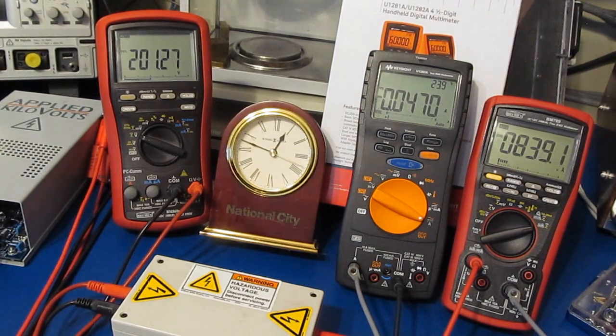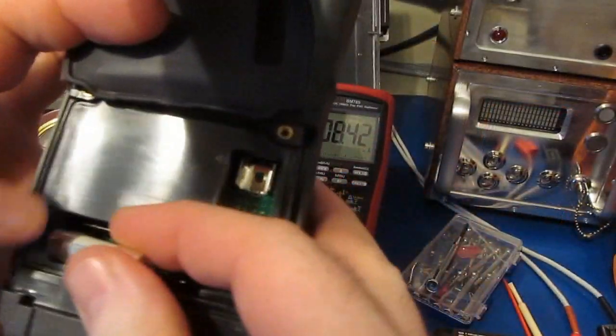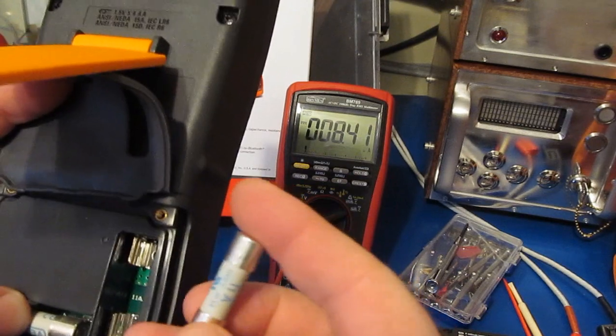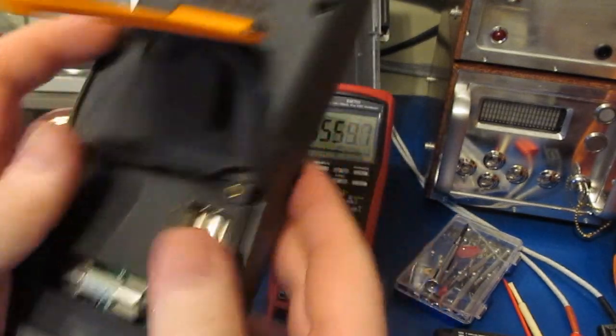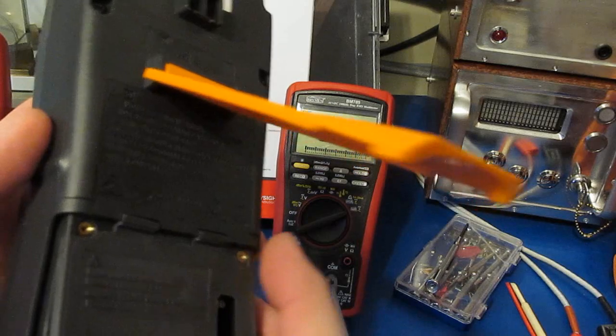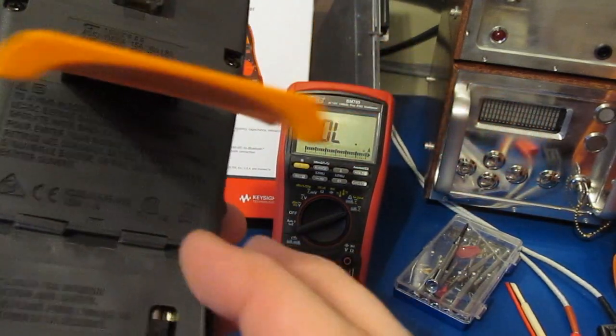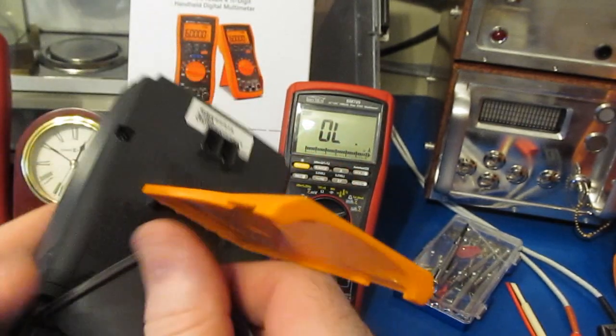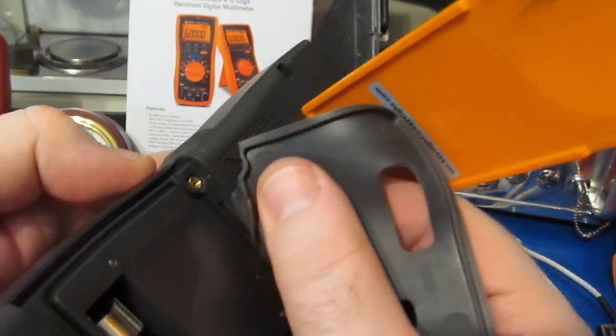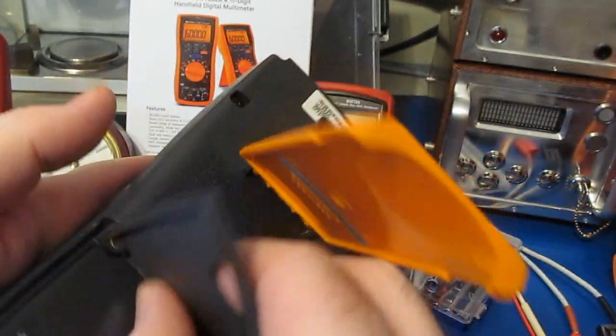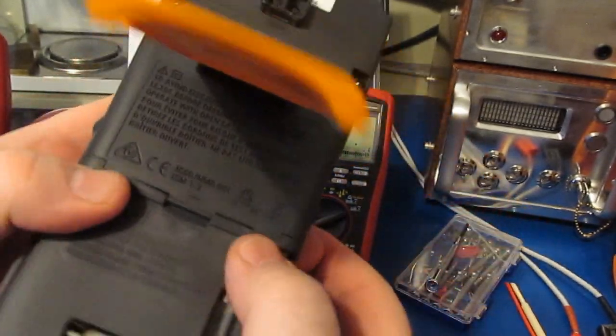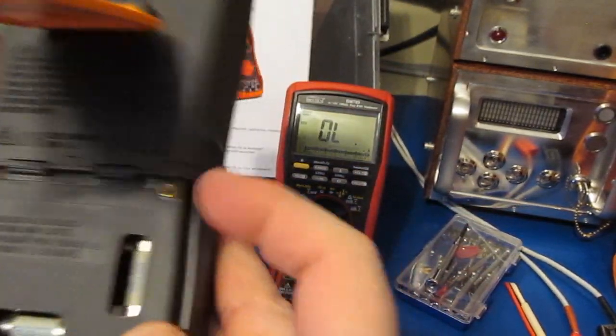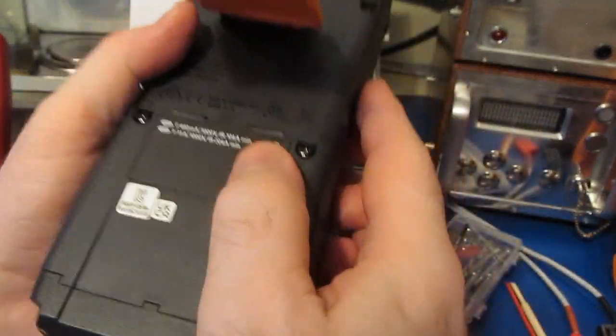Alright, there you have it. We'll turn our power supply back off. So let's go ahead and reinsert our two fuses, like so. One thing about this meter, again, because it's watertight, when you go to insert these gaskets, it's a bit of a pain to get them back into the groove. If I lift this back up, you can see right there the grooves that the gasket has to fit into. So you have to work it a little bit to get it down in those grooves, like so. But if you need a meter that's watertight, unfortunately, that's just one of the things you're going to have to deal with, is gaskets.